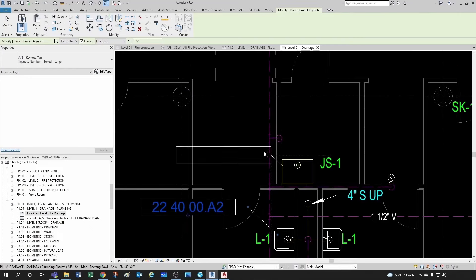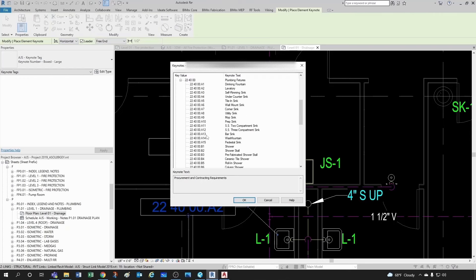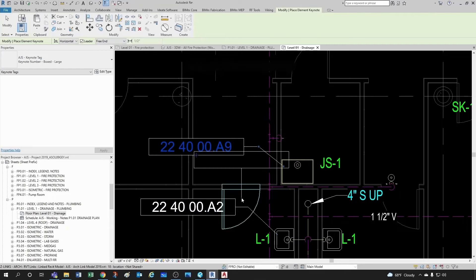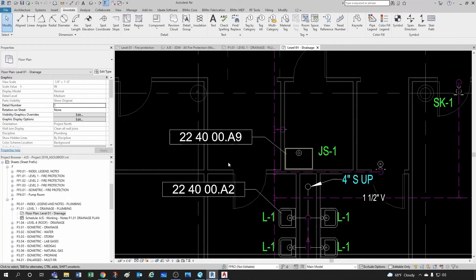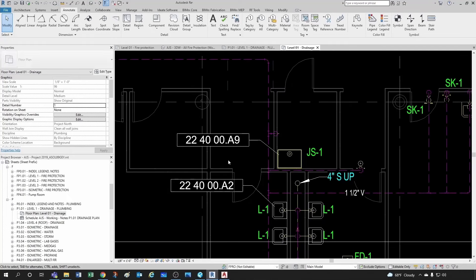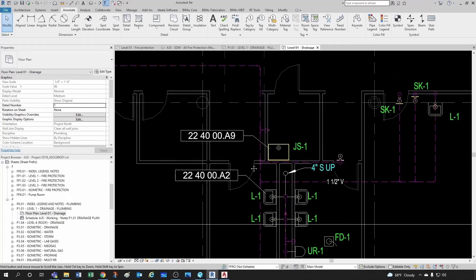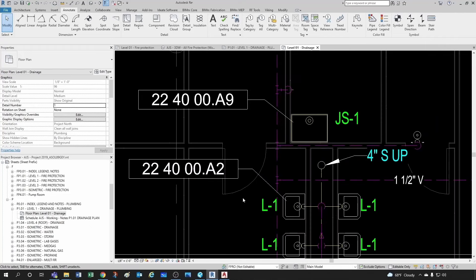You would go under plumbing Division 22, maybe plumbing fixtures, and select this lavatory — beautiful. Then you go to your mop sink, do the same, go under Division 22 again, plumbing fixtures, and there you go — mop sink. Very nice. Now that's Revit's ideal world. The reality is that for this to happen you would have to have your specifications perfectly in sync with your keynotes, tags, and drawings.